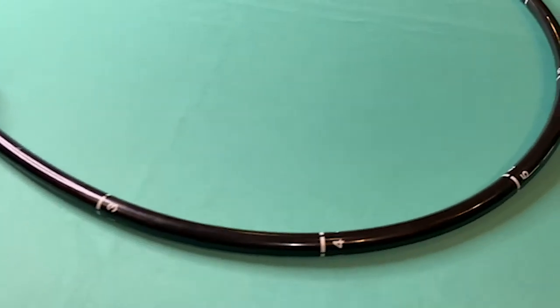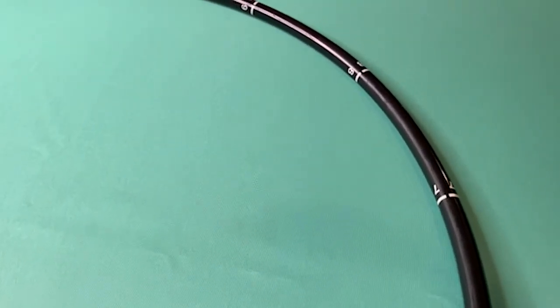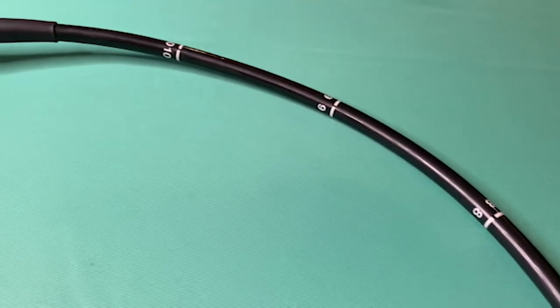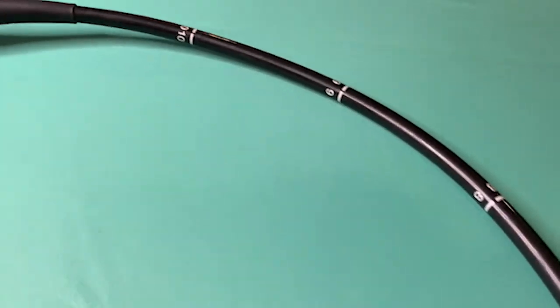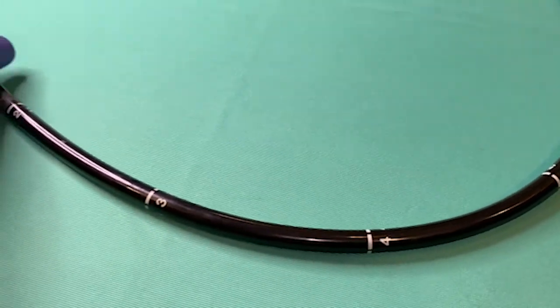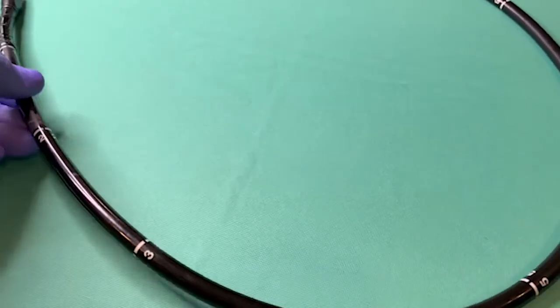It's normal for the luster to fade on an insertion tube as it ages, but the coating should not be peeling. Examine the numbering system for excessive wear or lack of visibility. Again, there may be a brown, crusty, or flaky material coating the insertion tube if an enzymatic cleaner is not part of the disinfection process.